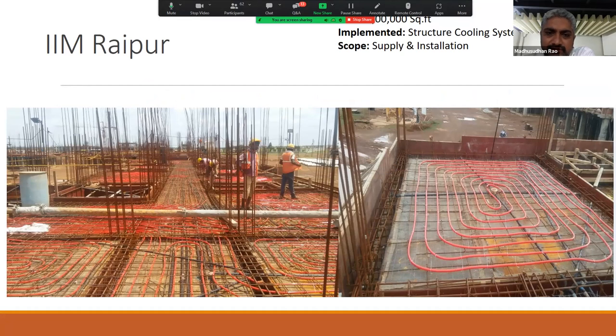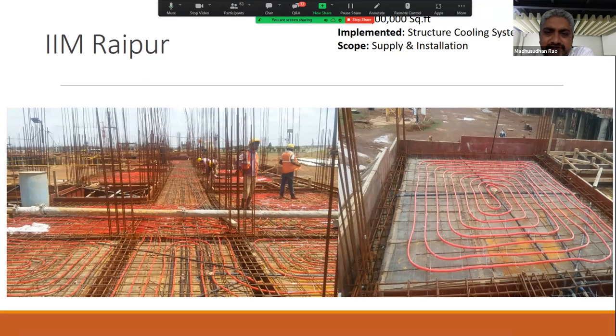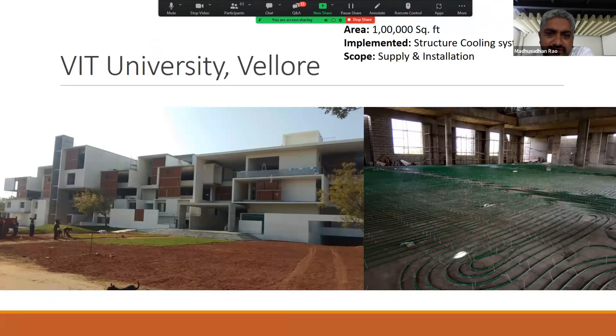A few examples of such installations. These are hostels in IIM Raipur, where since it's a government hostel, you can't give air conditioning. The same is being done even in IIT Hyderabad, where water at higher than the dew point temperature, actually the ambient dew point, which is much higher, is circulated just to flush out the heat. No RH control. You can keep the windows open. Fans can run just so that the building heat is flushed out.